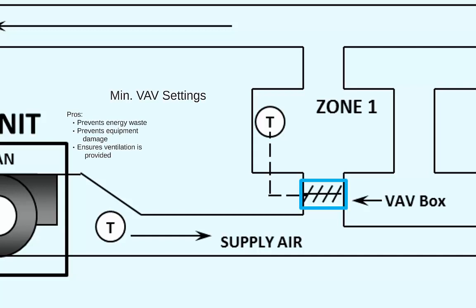First off, it prevents us from operating at low flows, which again can drive up the energy consumption and be bad for the equipment. Secondly, it prevents operating the fan in the surge region, which can be damaging to the fan. Lastly, it allows us to ensure an adequate amount of ventilation air is being provided to the space.